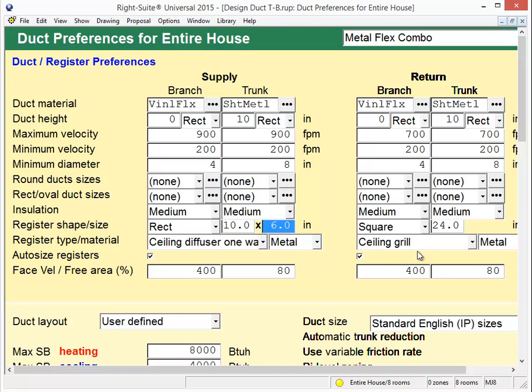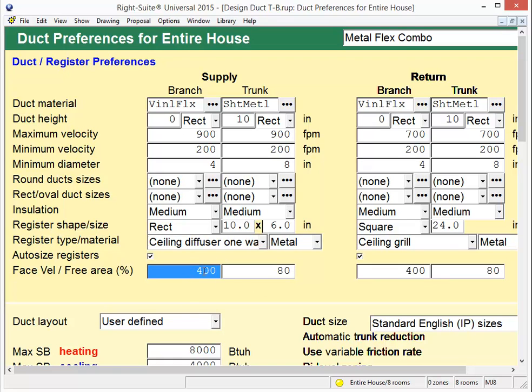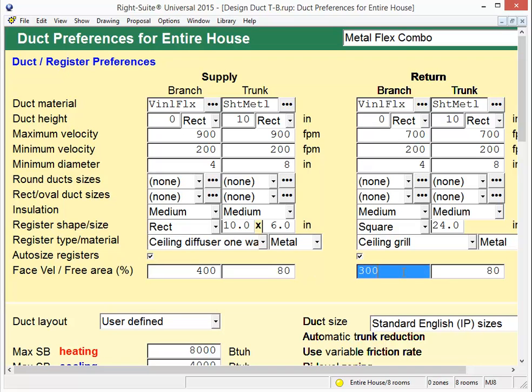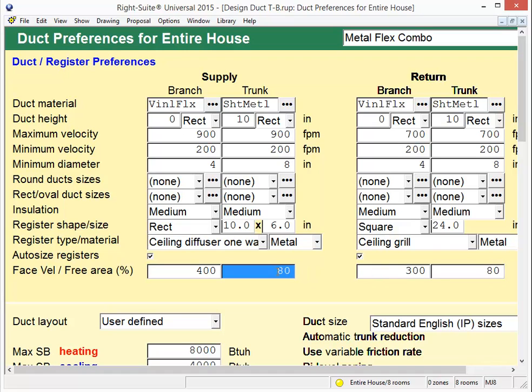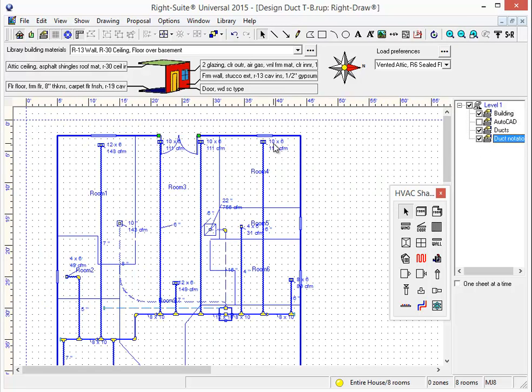On the return side, leaving it at square dimensions will simply change the square dimensions of the grill to achieve a certain target face velocity given a certain amount of free grill area. These are user-entered fields. If I want to achieve a 400 foot per minute velocity — this is in FPM — I would set that there. When the free area of the grill is known, I plug that in. So if I want a lower velocity on my returns to keep them quiet, I can plug that number in, and depending on what type of grill I'm using and its restriction in free grill area, I can change that percentage. Coming back to the drawing screen with that feature on and parameters set, when I turn on the duct layer, I can see that these grills are automatically sizing to my CFM needs. I can still change these sizes manually by going back to the duct preferences page and turning off the automatic sizing registers feature.